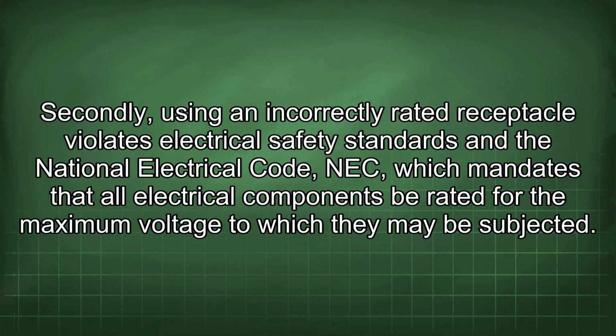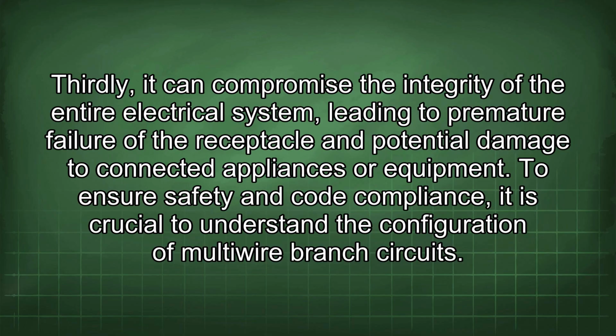Secondly, using an incorrectly rated receptacle violates electrical safety standards and the National Electrical Code, NEC, which mandates that all electrical components be rated for the maximum voltage to which they may be subjected. Thirdly, it can compromise the integrity of the entire electrical system, leading to premature failure of the receptacle and potential damage to connected appliances or equipment.